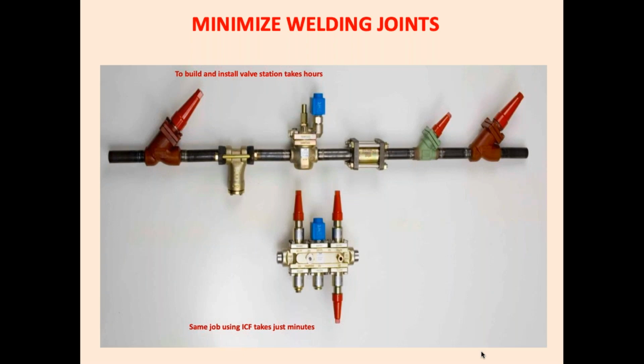Instead of that, now latest technology has controls which have everything built into a compact one piece. So only 2 welding joints are required. The fewer the welding joints, the fewer the chances of leaks. And not only that, the weight of the pipe comes down drastically. For example, in the drawing, this pipe shows very light, the top pipe, but you can't lift this. It has to be lifted by crane. It is a very heavy pipe. So if you fabricate it on the ground and try to fix it, you will have to lift it with the crane.